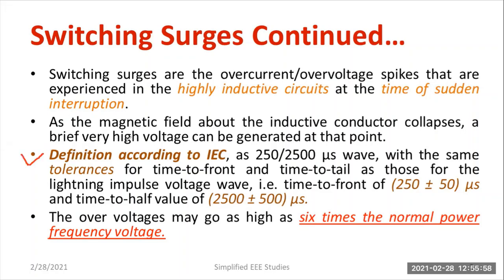According to IEC standard, switching surges are defined with a wave front time equal to 250 microseconds and wave tail time equal to 2500 microseconds. Including tolerance, the wave front time is in the range of 250 ± 50 microseconds, and the wave tail time including tolerance is 2500 ± 500 microseconds. Moreover, the overvoltage may go as high as six times the normal power frequency voltage — almost six times the magnitude can be produced due to switching surges.